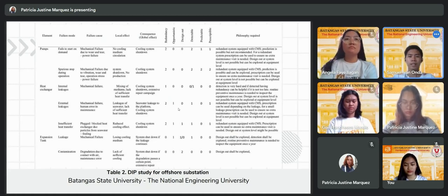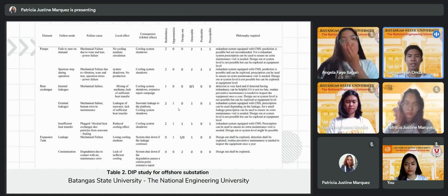For instance, the pump may be unable to start or it may experience a spurious halt because of mechanical failure. These failure modes will prevent the pump from performing its role of circulating the cooling medium, which will result in the shutdown of the cooling system. By using redundant pumps, it is possible to avoid the shutdown that would otherwise be the principal global effect of such failure. Since the breakdown must be rectified promptly and cannot be regarded as a postponed occurrence, maintenance is not a viable choice.